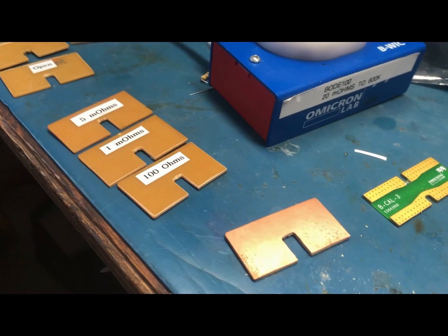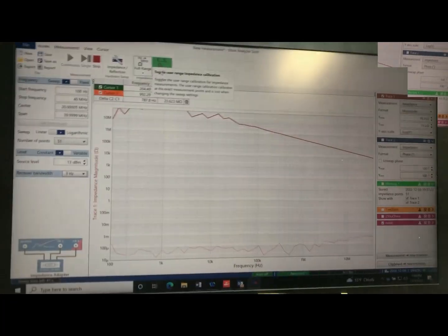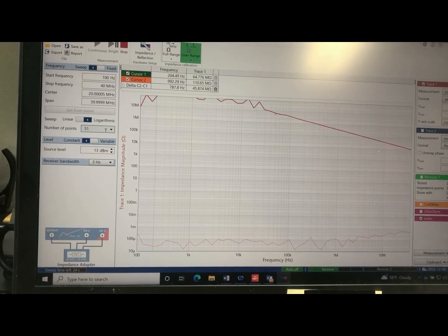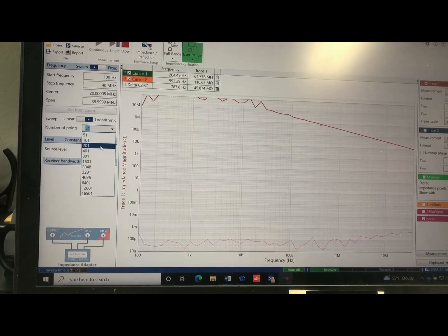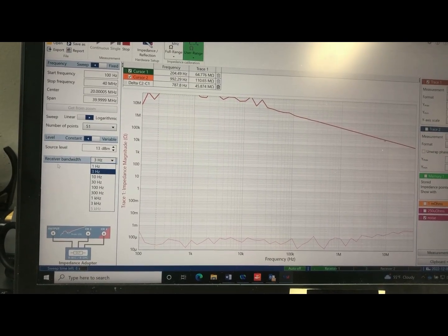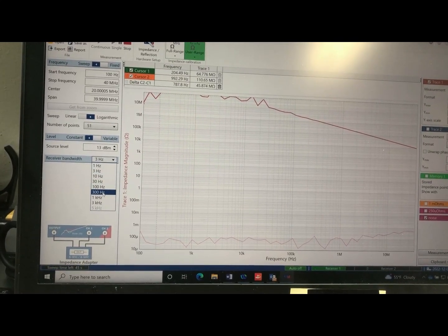So the first calibration that I'm going to do, here's another thing that I'm going to do that's a little bit different. Typically when you bring up the B-WIC menu, the number of points is usually, I believe, 200. What I do is I set it to 51 points, and I reduce the receiver bandwidth from 300, which I believe is the default.